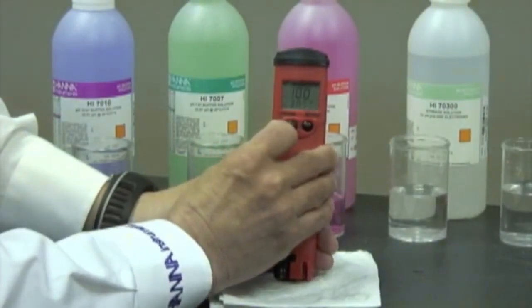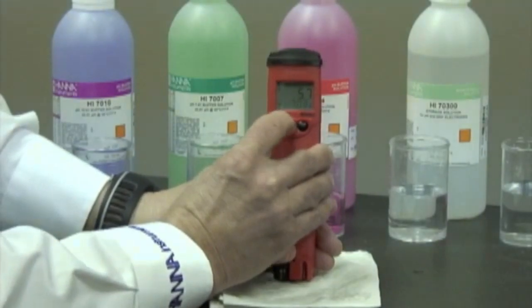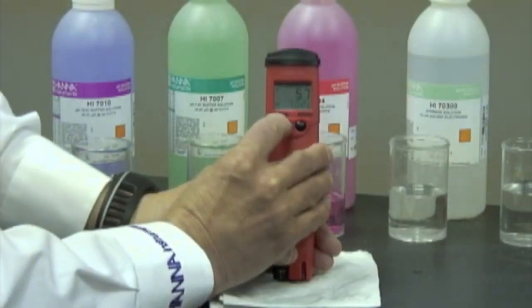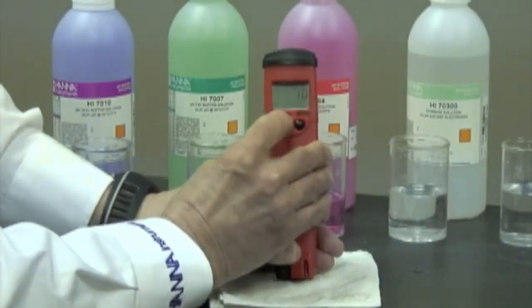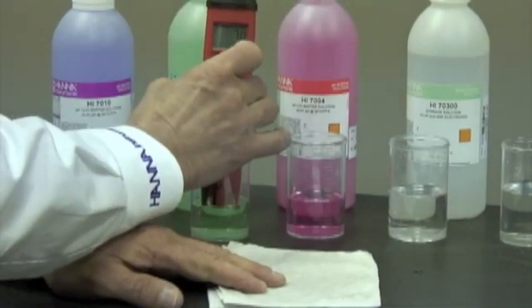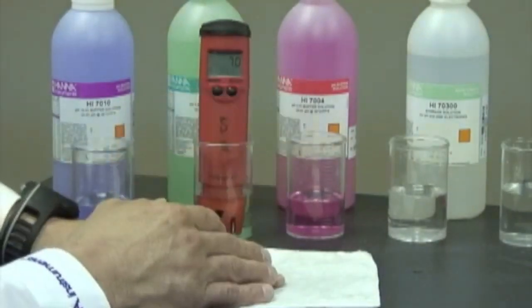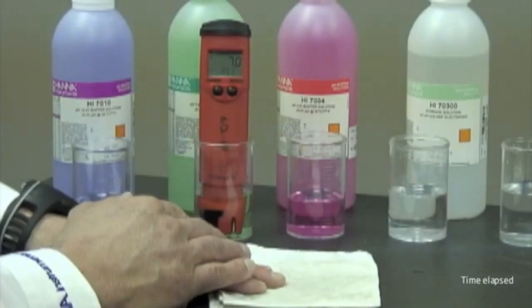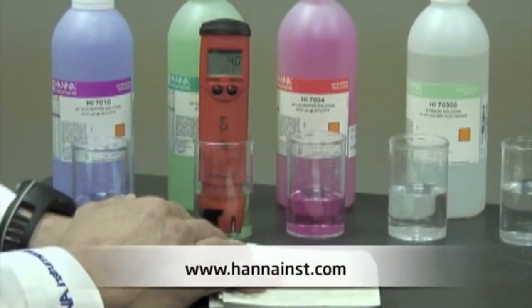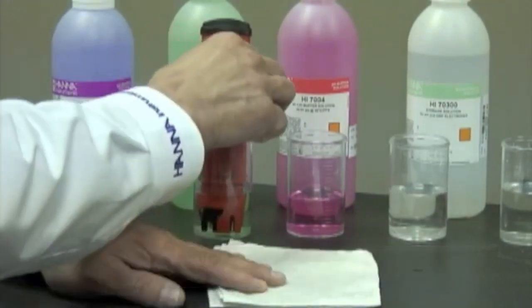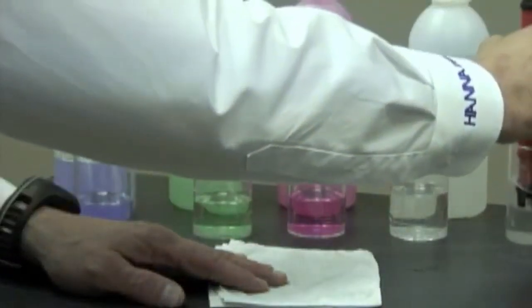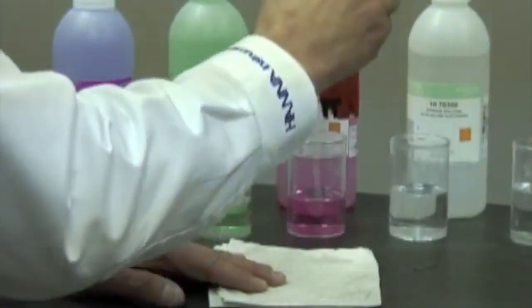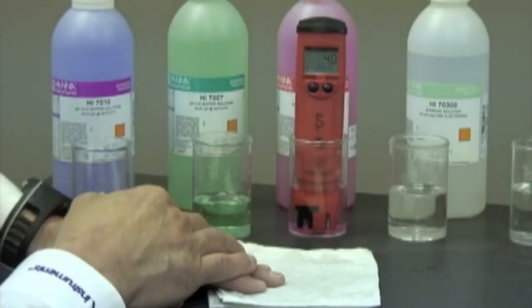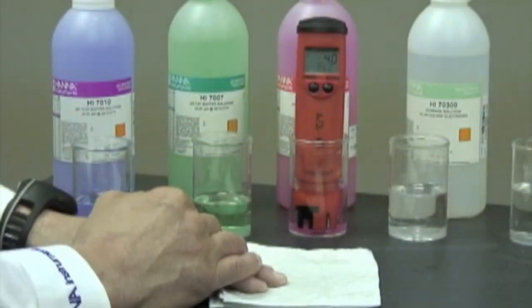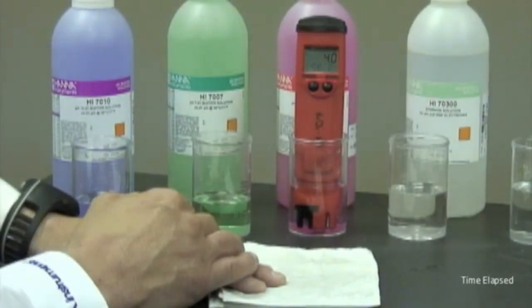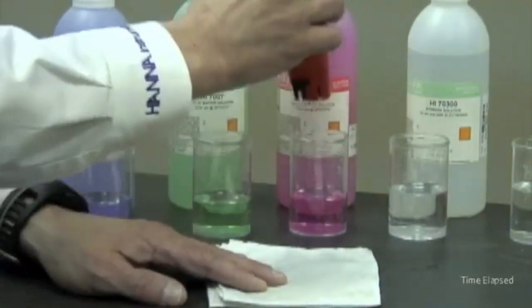I'm going to turn the meter on, put it back into its measurement mode, and then I'm going to hold the mode button down for 3 seconds until it gets into calibration mode. Now it's asking me, in this case, to use a number 7 buffer. Now it's recording. The meter is now done recording at number 7. So I'm going to rinse it off in water once again, get that buffer off. I'm going to put it into number 4 because that's what it's asking for. And now it's recording at number 4. Okay, we're ready to use our meter.